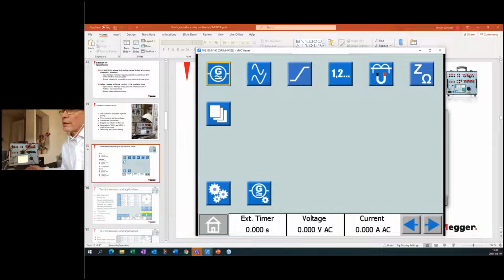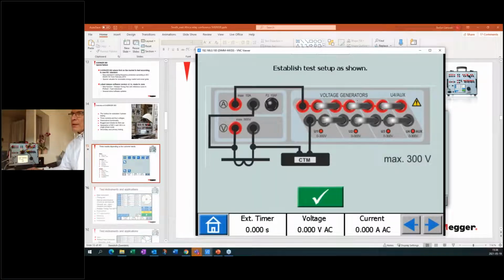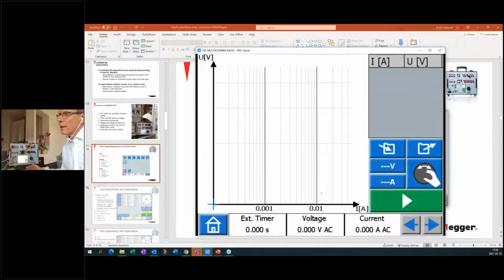In this case, I'm already connected, so I will start with the CT magnetization instrument. I click there, and the Sverker 900 tells me how to connect. Now we are using only the voltage output, and they shall be used in parallel connection. I have already made this connection. Maybe it's difficult for you to see, but it's connected here. Then I continue, and I can run in automatic mode or manual mode. If I run in manual mode, I turn the knob here, but I will run it in automatic mode.